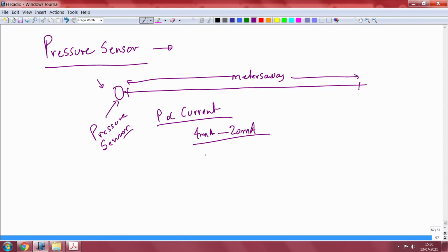In fact, the whole communication between the pressure sensor and the unit itself is called 4 to 20 milliampere communication. It is also interchangeably used as a communication protocol. So 4 to 20 milliampere is a very old protocol, and you can think of the lowest pressure as something like 4 milliamperes and the highest pressure as 20 milliamperes, and anything in the middle is actually measurable. That essentially gives you the same analog quantity out there.